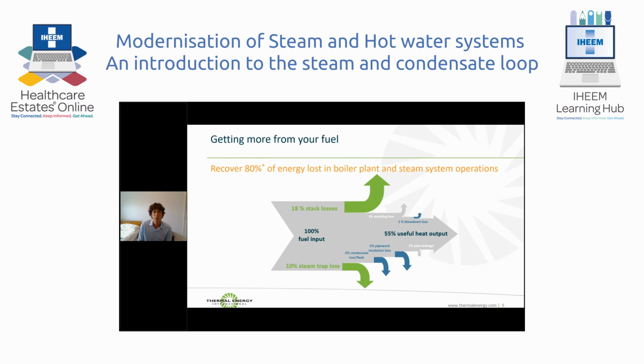If we take a closer look at our individual facilities within the hospitals and the estates that we run, this is a Sankey diagram for a typical steam boiler. You can see here there's a considerable opportunity for optimization in an unoptimized system. For 100% fuel, the natural gas or whatever other fuel we're buying, we typically get 55% useful heat output. We're going to talk through how you can recover at least 80% of the energy lost in these boiler plant and steam system operations. I know many facilities are considering decentralization and moving to hot water systems. However, the vast majority of these savings can be achieved through upgrading the existing infrastructure and rationalization.